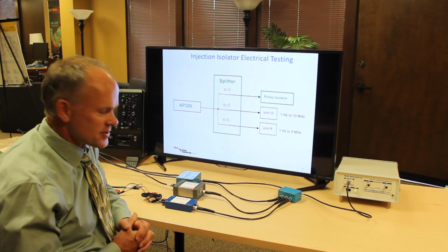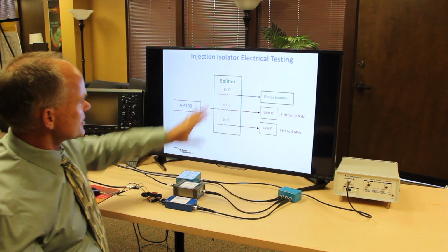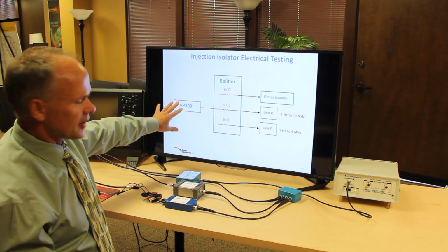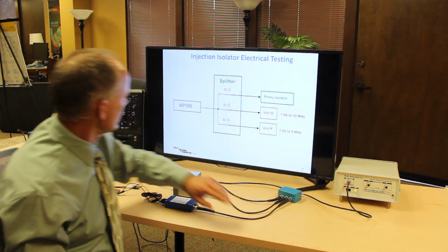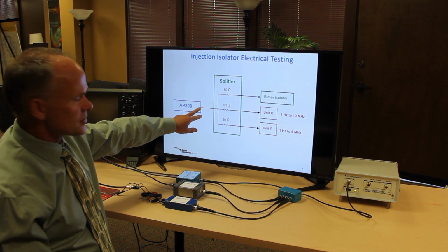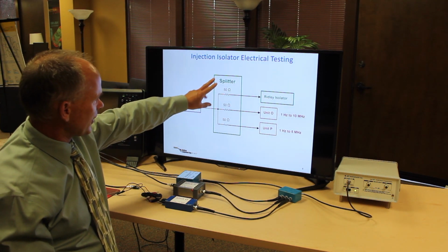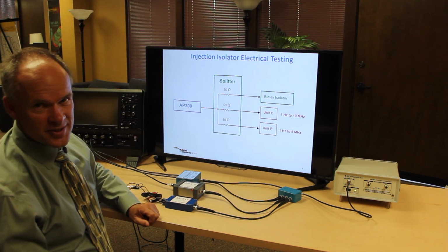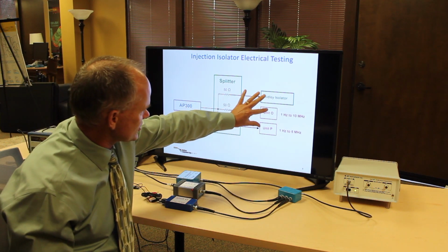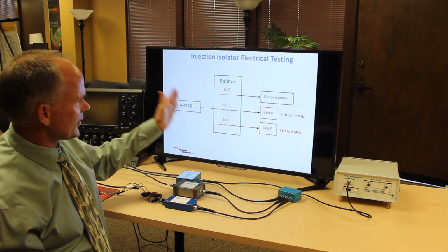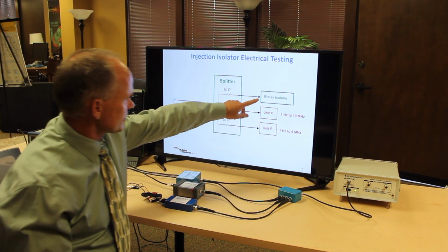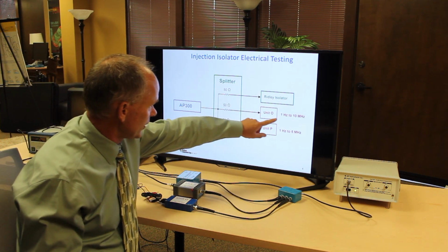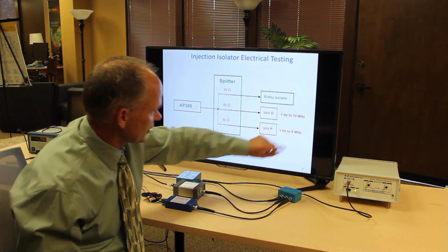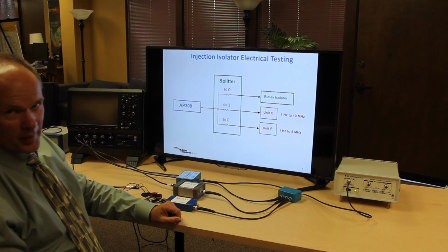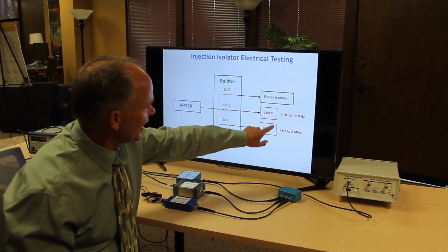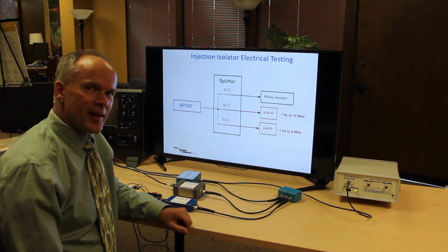What we're going to do now is test these three isolators electrically. This is the setup we have here. First we start with the AP300, that's our instrument on the right, and we take the source output from that, using it as an RF power amplifier, and drive a splitter with 50 ohm resistors in it, and those splitters drive each of our isolators, so we make sure they're all getting the same drive signal. Here's the Ridley isolator, Unit O at 1 Hertz to 10 megahertz, and Unit P at 1 Hertz out to 5 megahertz. We're going to look at the actual output of each device to see how they perform with this drive.